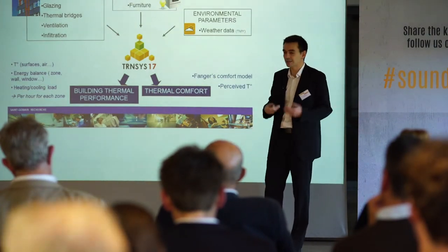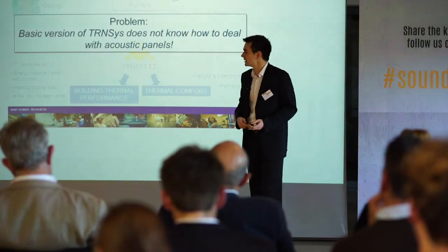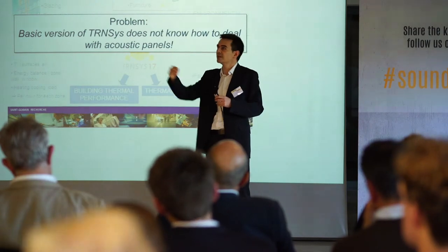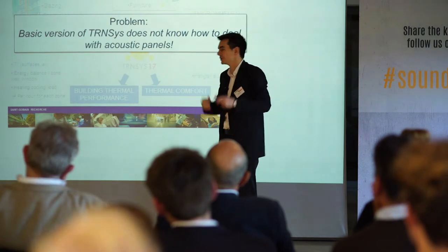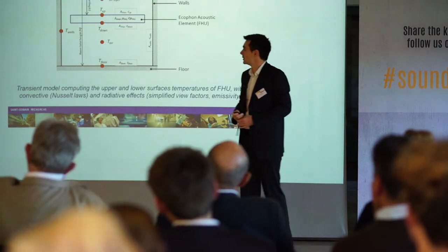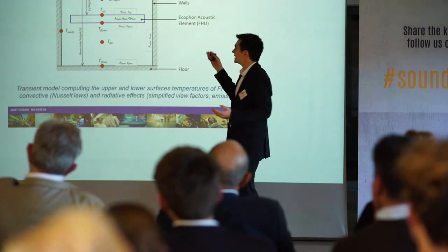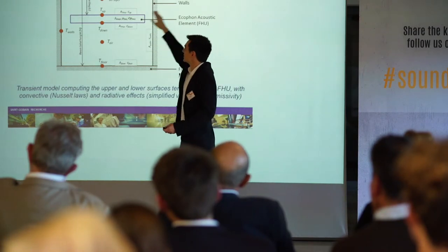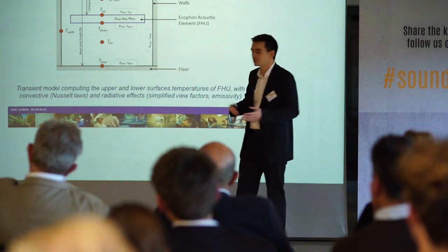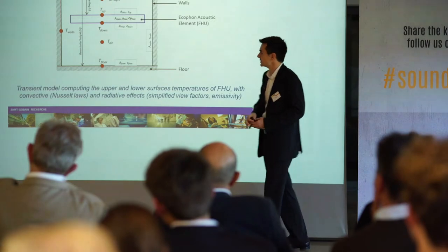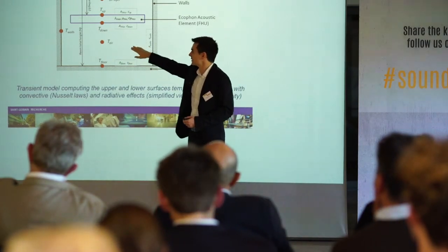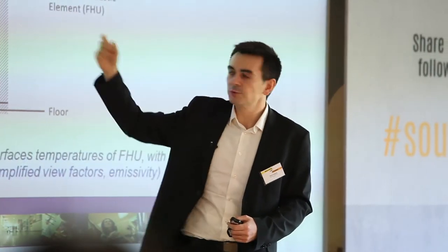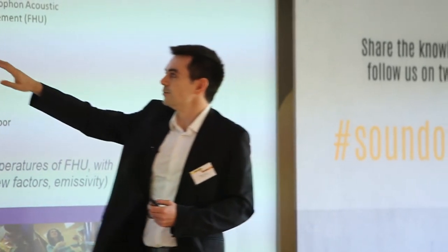It's a simulation software that helps you study the behavior of the building. The problem is that the basic version of TRNSYS does not know how to deal with acoustic panels, because in TRNSYS it's very difficult to model such a surface — a small surface with a lot of voids around everywhere. So what we did: we worked on a thermal model of acoustic elements in buildings for TRNSYS. We consider a room with a panel in the center, wrote some equations accounting for the temperature difference below and above the panel, the emissivity, the surface characteristics, and we tried to include the laws for convective and radiative exchange between the panel and the surroundings.